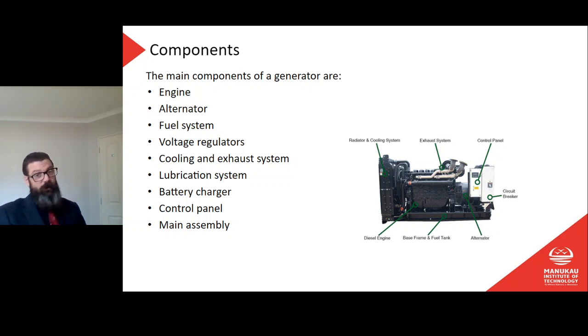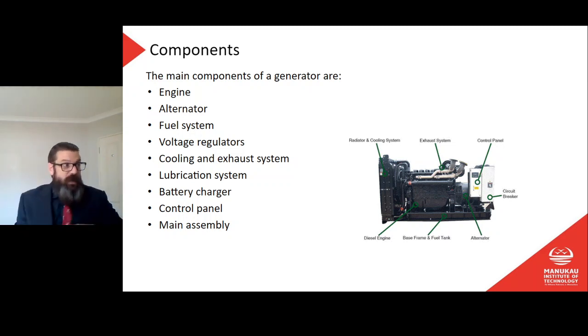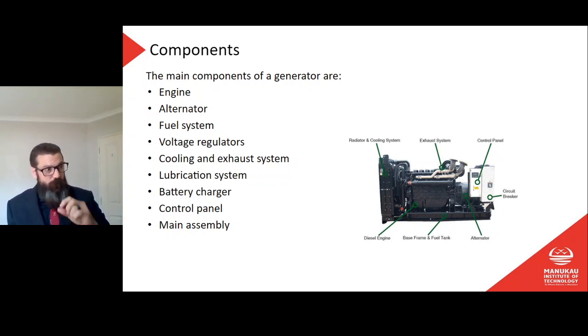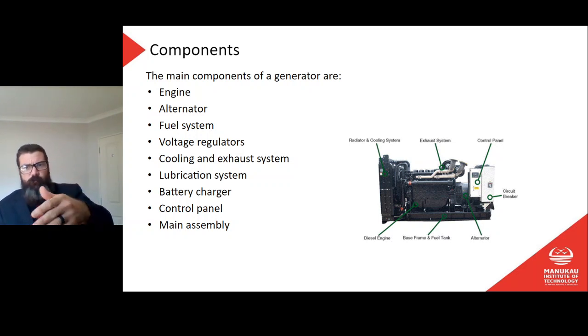There's in fact a little spring linkage between the governor. The governor is the mechanical component that the voltage regulator is talking to. There's a little spring inside the governor that, when it got stretched, would react too slowly. So the voltage regulator is telling the governor, put more fuel in. The governor would say okay, and then it would move, but because the spring wasn't responding quickly enough, the voltage regulator would say, you still haven't given me more fuel, I need more fuel. So the governor would say okay, and by the time the governor caught up with what the voltage regulator was telling it to do, now it's running too fast, and so the voltage regulator would say, stop, give less fuel, and so it would cut it back.